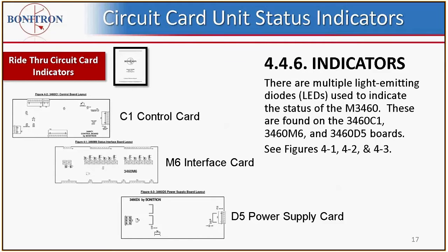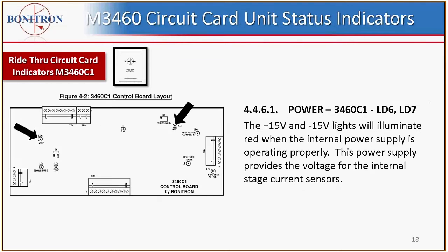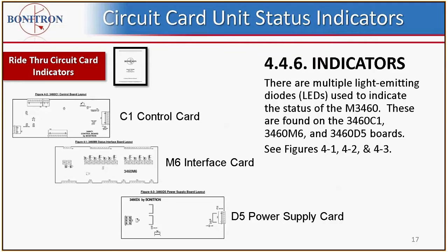I talk about the 3534s a little later. There are some differences. There are no card indicators on those units, and the 3460s are what we're discussing in the next several slides. The three cards are the C1 control board, the M6 interface card, and the D5 power supply card. I'm going to review the indicators on all three cards, and once you have a clear understanding of what the indicators are on all the cards, it really helps you down the road if you're having an issue with the ride-through or if you have a fault you're trying to determine.